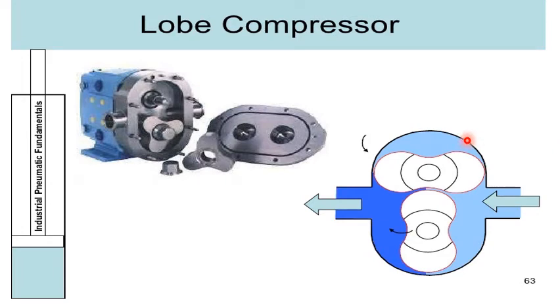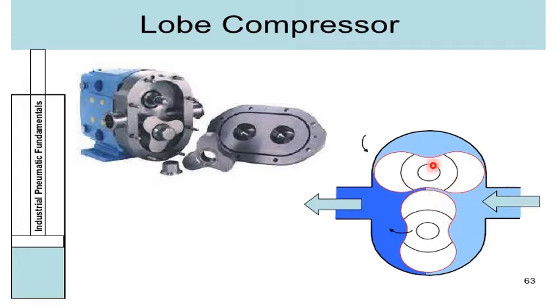Next is the lobe compressor. It consists of two rotors mounted inside the casing. The rotors are meshed with each other — one is the driver and the other is the driven. When the driver rotor is rotated by a prime mover, the driven rotor also rotates. Air gets trapped in the pockets between the rotor and casing and is carried by the rotors from the inlet to the outlet.